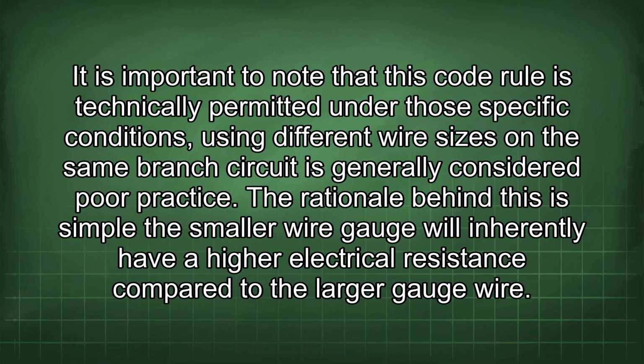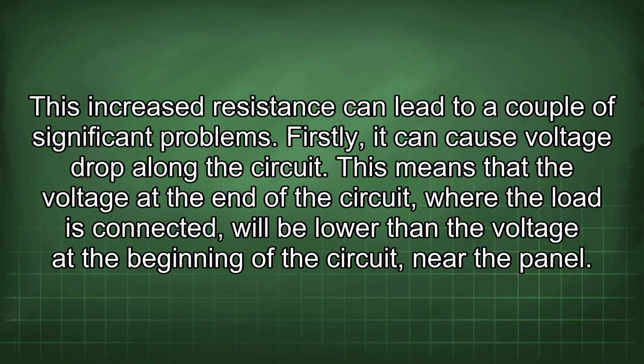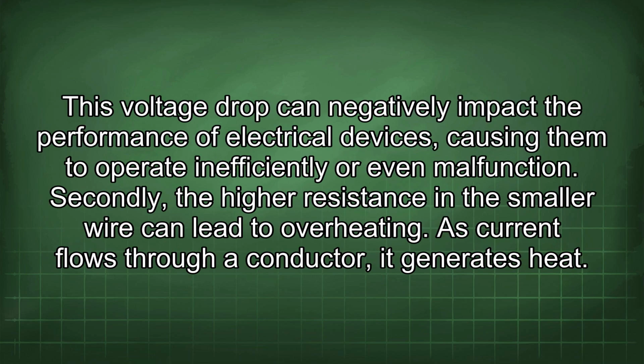The rationale behind this is simple: the smaller wire gauge will inherently have a higher electrical resistance compared to the larger gauge wire. This increased resistance can lead to a couple of significant problems. Firstly, it can cause voltage drop along the circuit. This means that the voltage at the end of the circuit, where the load is connected, will be lower than the voltage at the beginning of the circuit near the panel. This voltage drop can negatively impact the performance of electrical devices, causing them to operate inefficiently or even malfunction.